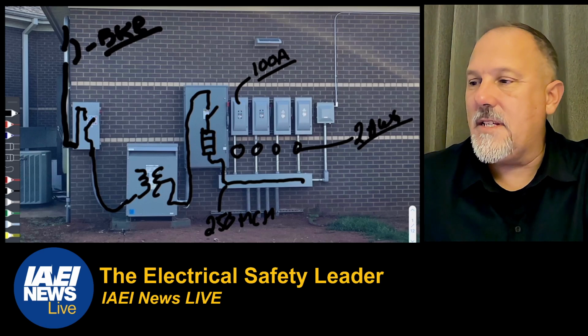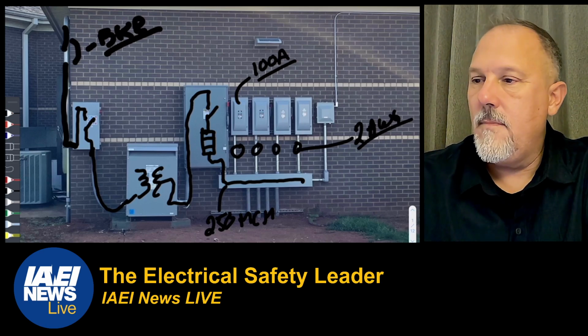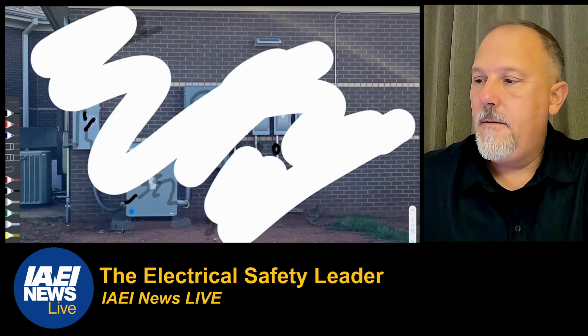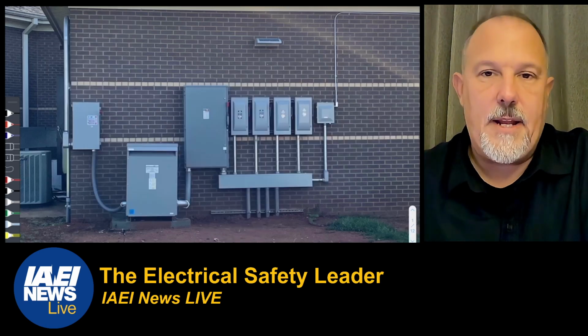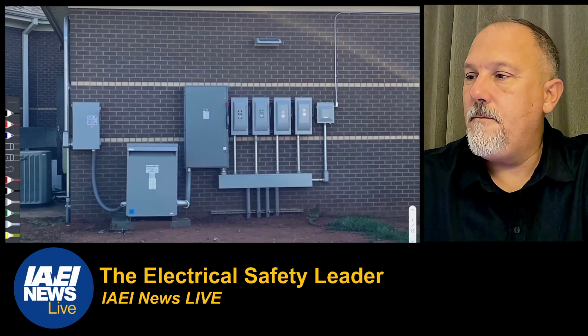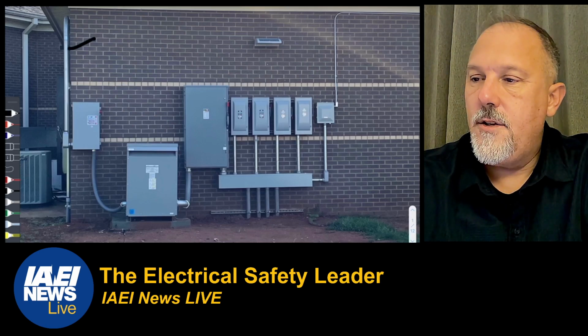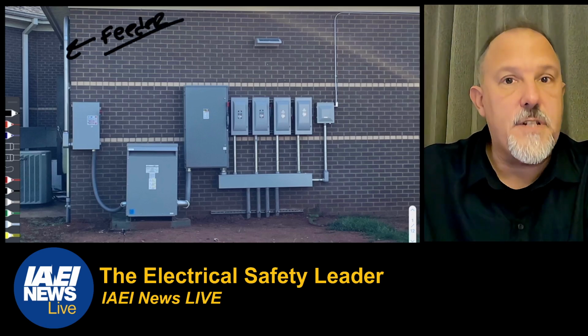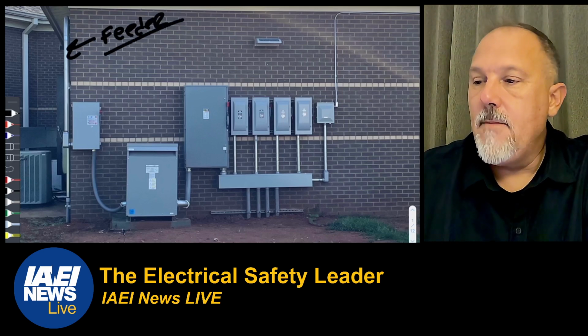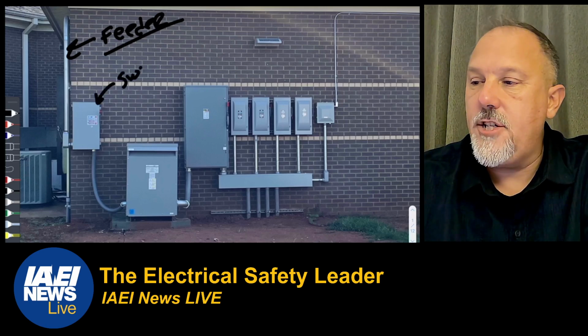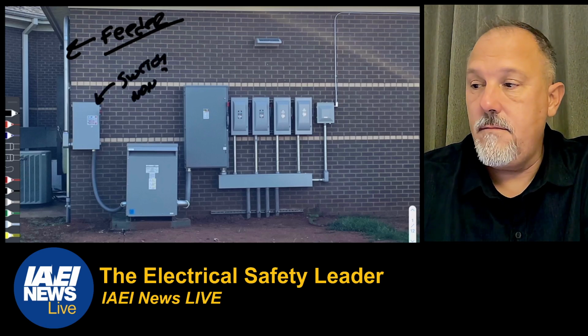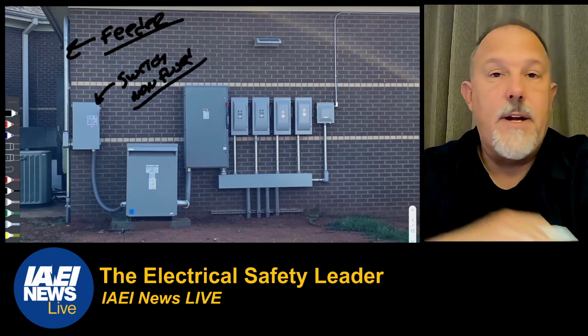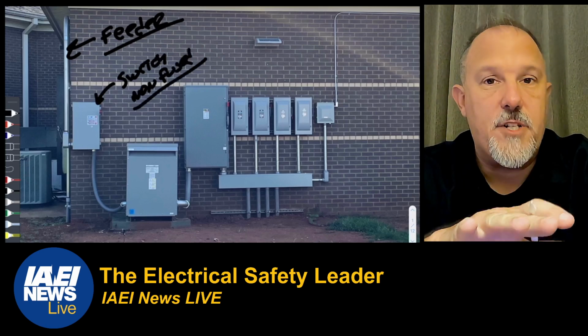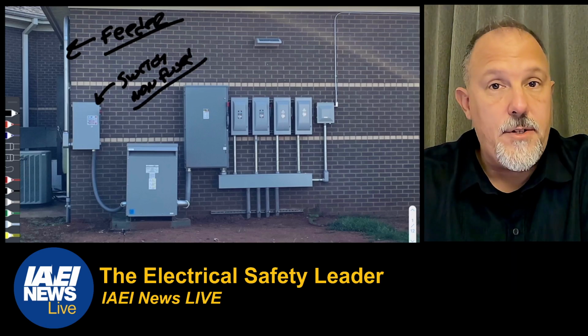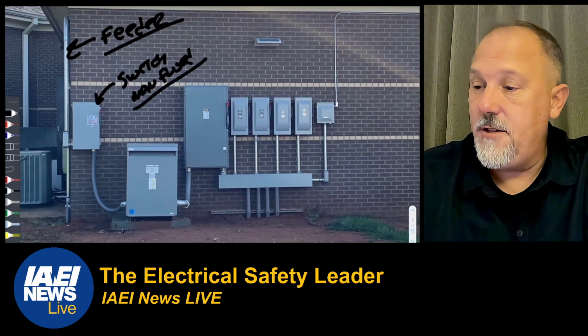So we know all of this equipment is feeder equipment, right? So that is a feeder, because that feeder is fed from the service equipment on the other side of the building. We know this is just a switch, non-fused, right? So what do we have to think about from a non-fused switch perspective? We have to understand available fault currents, short circuit current rating of that switch.